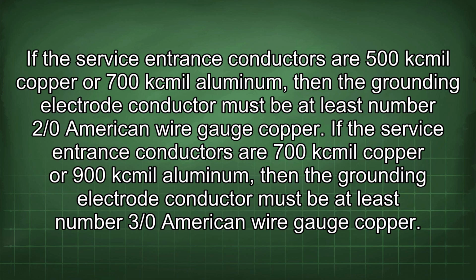If the service entrance conductors are 500 kcmil copper or 700 kcmil aluminum, then the grounding electrode conductor must be at least number 2/0 American wire gauge copper. If the service entrance conductors are 700 kcmil copper or 900 kcmil aluminum, then the grounding electrode conductor must be at least number 3/0 American wire gauge copper.